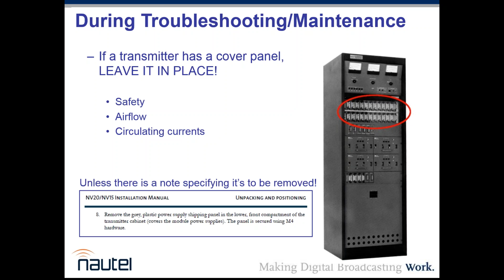The other advantage is that the lockout serves to remind you of things as you go to put the key in the lock to remove it. You ask yourself, did I close the interlock, or switch the remote back on? It can actually help by slowing you down when you're tending to run at 140 miles an hour trying to get things back on the air.